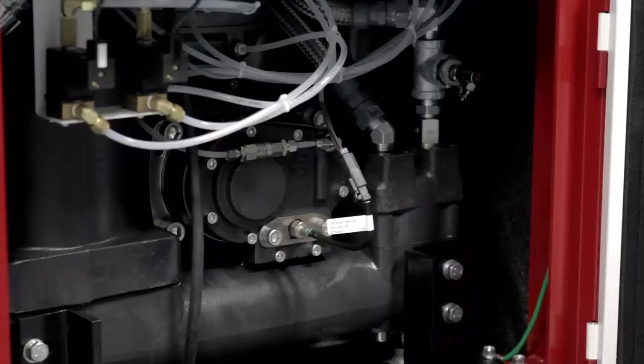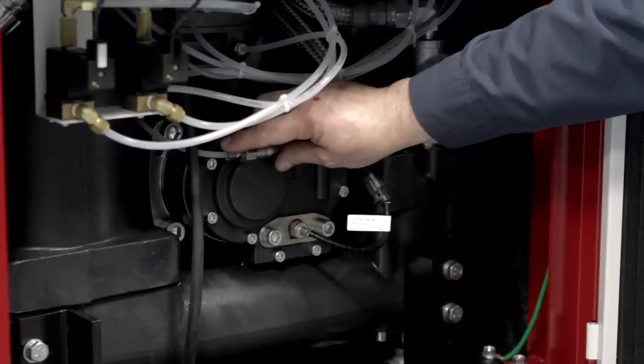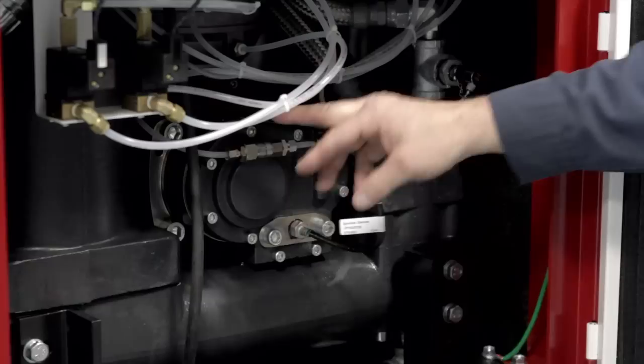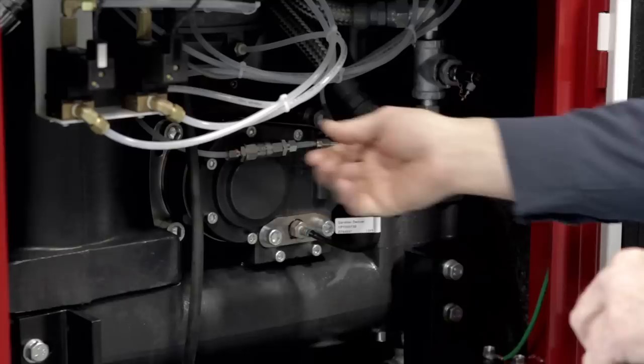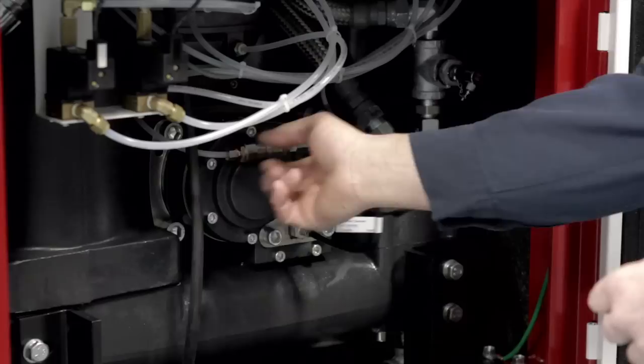We also have an inline scavenge check valve here. It's a spring-loaded orifice fitting that lets the oil from the separators return to the air end while it's running, through an orifice and a screen. We do like to remove this, take it apart, and clean the screen that's in there and make sure the orifice is open whenever we do a PM. Reassemble it, put it back in, and when we start the unit we always look to make sure we have a vapor of oil going through the line to confirm it's operating correctly.